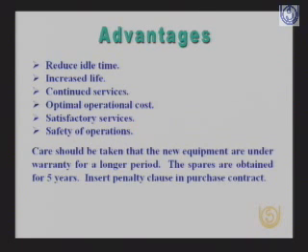When getting the equipment, we have to also take care that we try to extract a longer warranty, and that the spare parts are also taken, which can last you for some time, rather than not asking for any spare parts from them. And then insert penalty clauses in the purchase contract: if you do not turn up within, say, 24 hours, if you are a little away from a big city, that if your X-ray machine or your CT scan is down, and once you call them, they must be there as early as possible, or you can define a time, say 24 hours, and if they don't come in 24 hours, you can put the penalty on them.